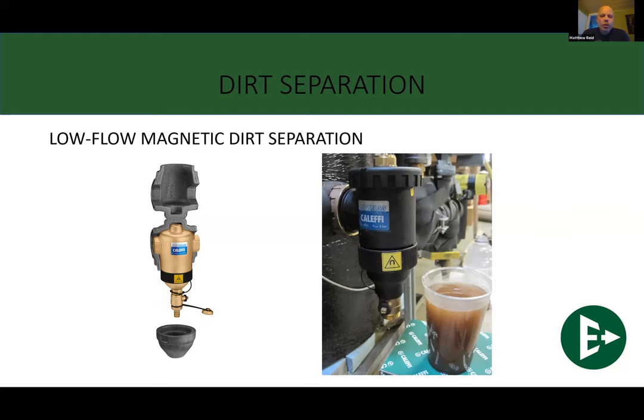Now, with regards to a dirt separator, I want that to be the last thing that the boiler sees. So the water goes out through the air separator, goes through its pumps, goes through its heat emitters, through whatever it wants, and just before that water gets back to the boiler, I want it to go through a dirt separator to make sure that everything it may have picked up through the system does not make it back to the boiler. We get it out before that. Let it pick up the dirt from everywhere else if it needs to, but it will not hit that heat exchanger in the boiler. You're going to be taken care of there.